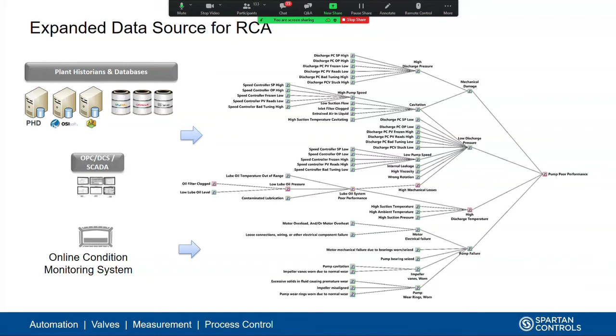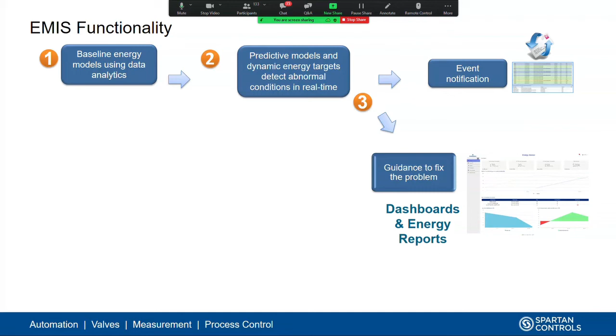So we can then incorporate, well, there's a problem with the pump because now you've got a bearing failure, or there's a problem with the pump because there's a misalignment issue, or there's a problem with the pump because it's got soft foot and it's wobbling around, it's loose, right? This is the type of information that we would not normally see. So now, bringing this back to the EMIS conversation, our traditional EMIS was just giving us a quick indication that we've got a fault condition. If we can start incorporating these root cause analysis models, we don't have to do the troubleshooting.